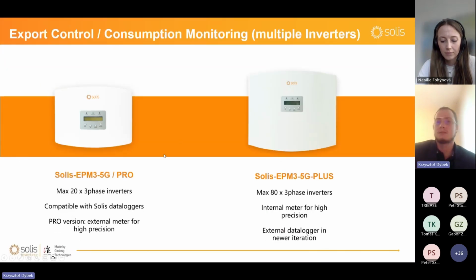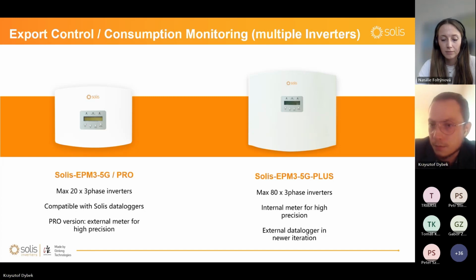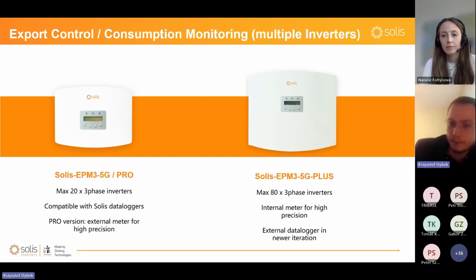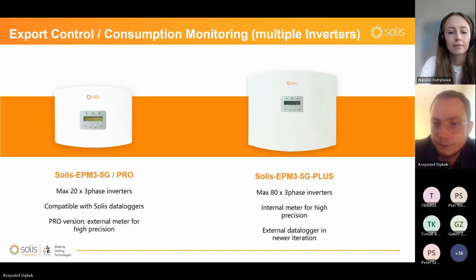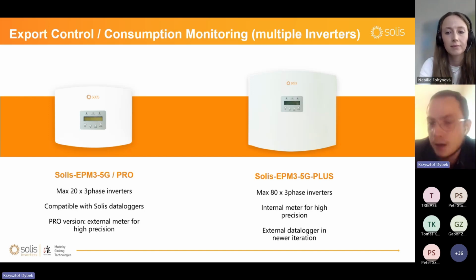And about EPM itself, if you have 2 or more inverters on site, you need to have one external EPM. It is just not possible. There is only one master. The device is slave. So EPM becomes a master device, and you connect your inverters together using daisy chain, or as I call it, cascading scenario.